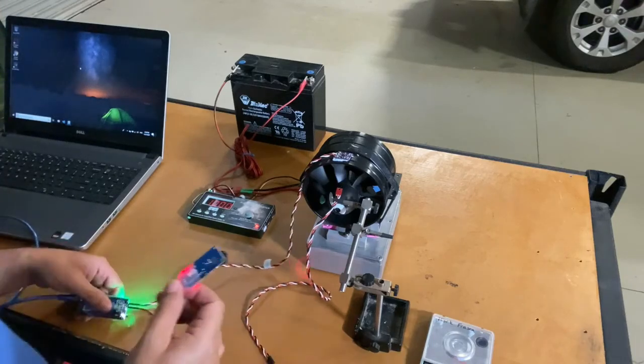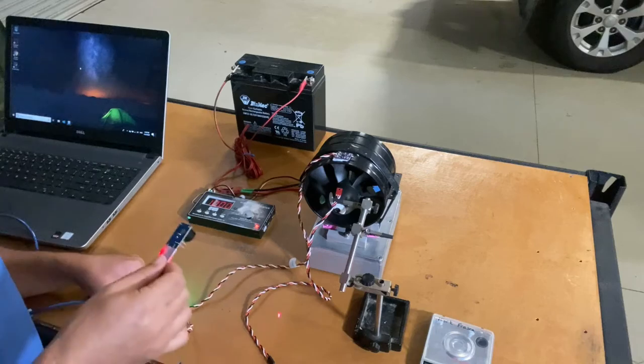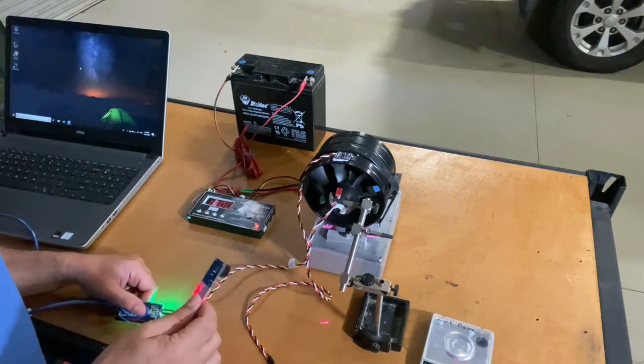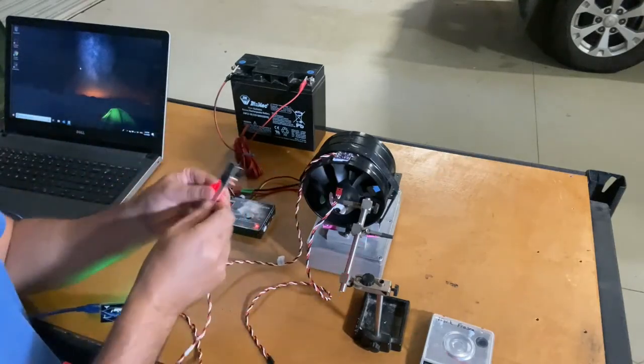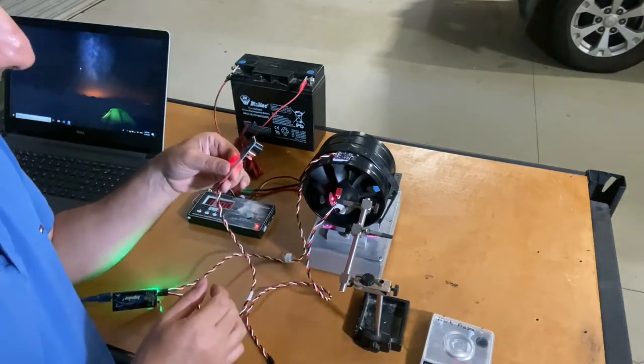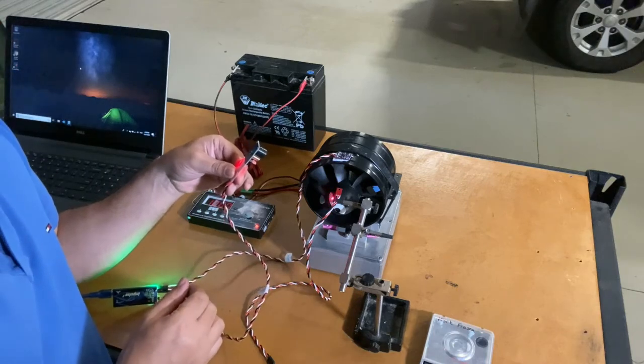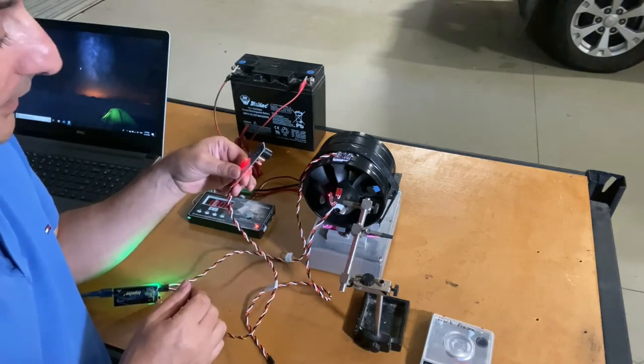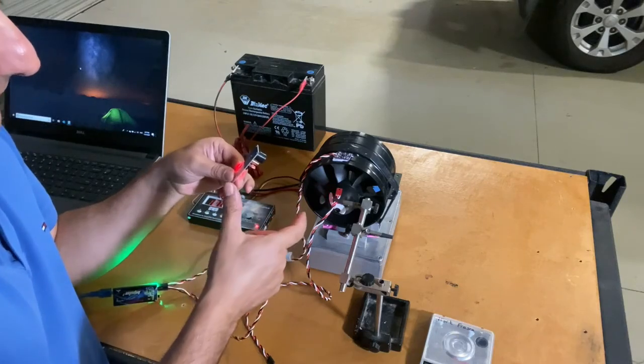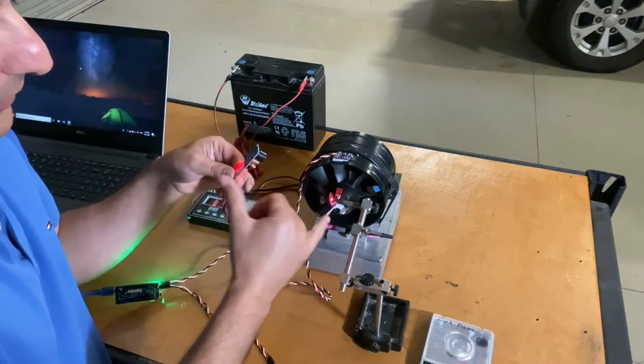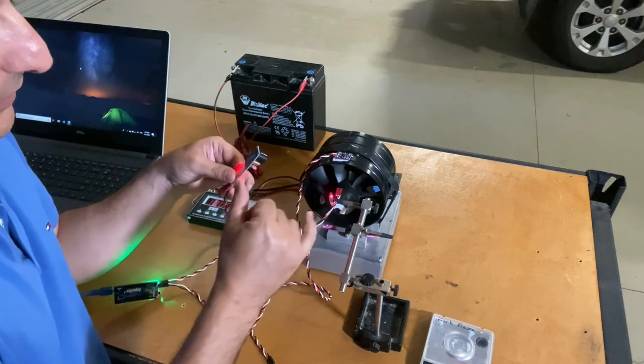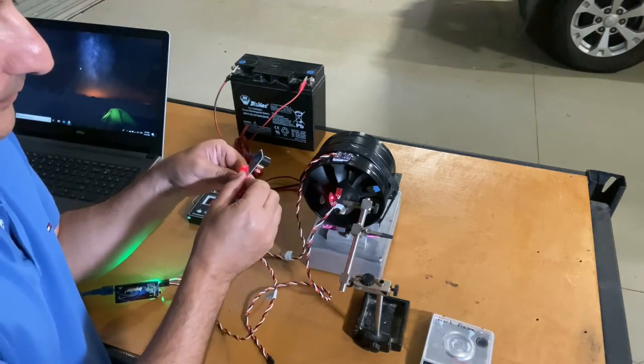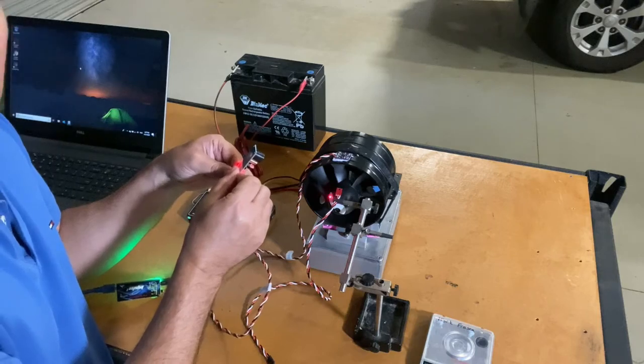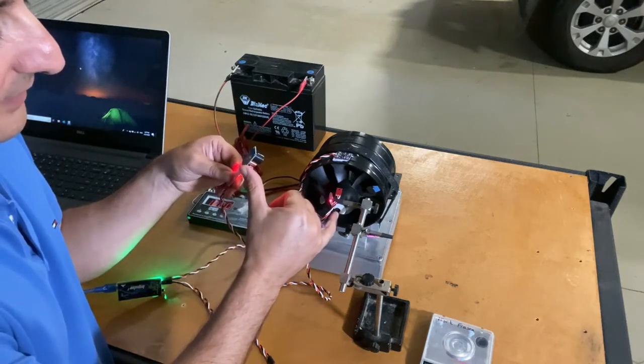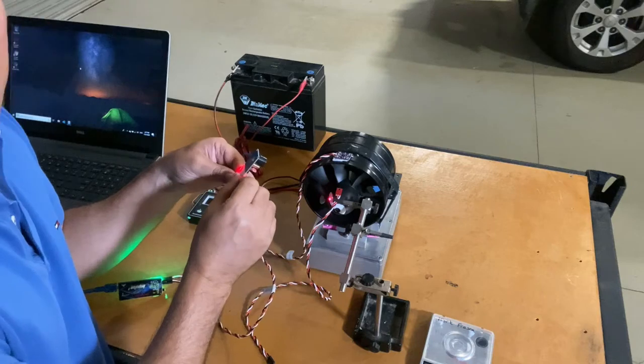As soon as you plug it in, you'll see, I don't know if you can see that on the camera, the red dot next to the green light. Right, so when that is actually installed onto the hub, I'm not sure if you guys can see that. Yep. There's a bit of a catch in terms of how close you set this to the hub. So essentially what I find is that when the sensor is positioned at a slight angle and maybe 10 to 15 centimeters away from the hub seems to be a sweet spot.